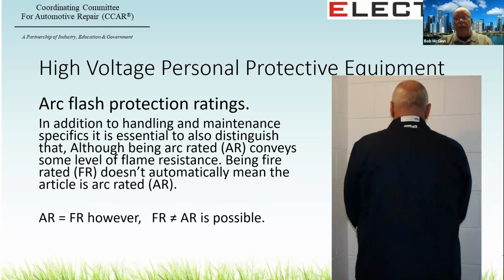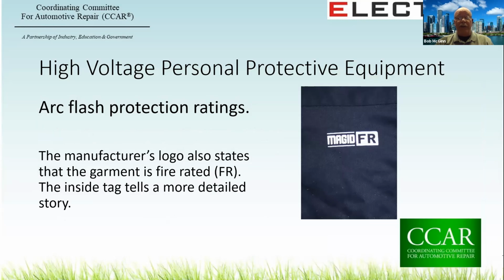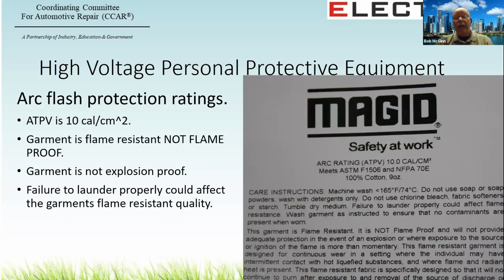At the same time, it is important to distinguish that while being arc rated makes an article fire resistant, being fire resistant doesn't necessarily make you arc rated. Now, in the back of this jacket, the tag tells the story. But as we move in closer, here the logo says fire rated, but let's have a look at that inner tag.